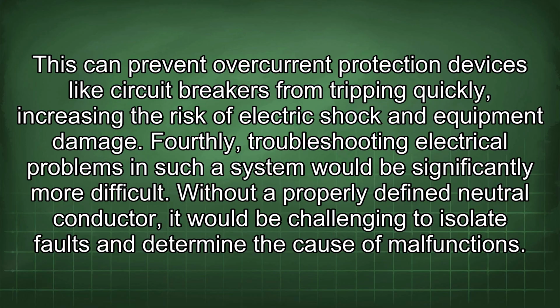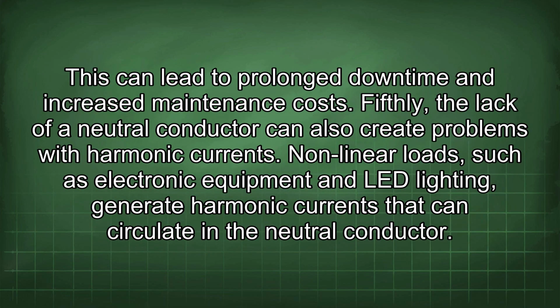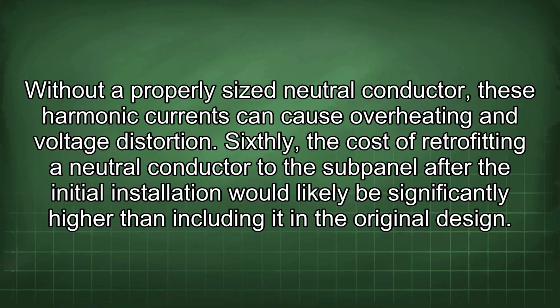damage. Fourthly, troubleshooting electrical problems in such a system would be significantly more difficult. Without a properly defined neutral conductor, it would be challenging to isolate faults and determine the cause of malfunction. This can lead to prolonged downtime and increased maintenance costs. Fifthly, the lack of a neutral conductor can also create problems with harmonic currents. Nonlinear loads, such as electronic equipment and LED lighting, generate harmonic currents that can circulate in the neutral conductor. Without a properly sized neutral conductor, these harmonic currents can cause overheating and voltage distortion.